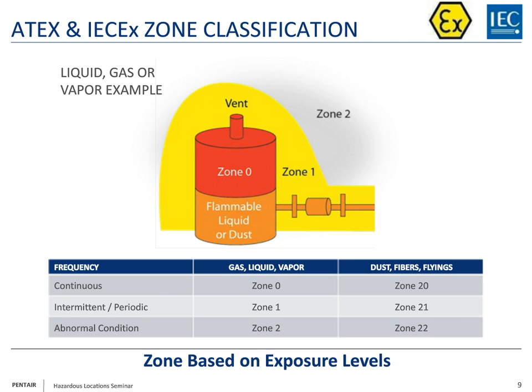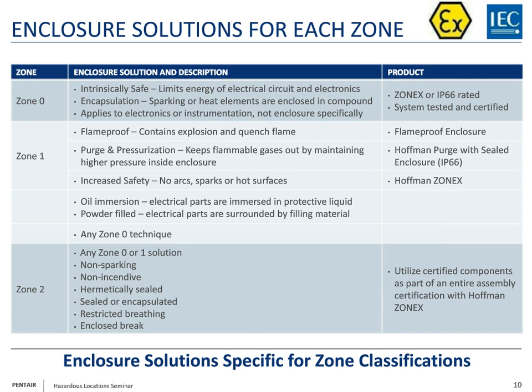So if we focus on zone 0, 1, and 2, what types of solutions are available to you? Well, like I said before, a zone 0, typically you don't see a lot of control panel applications there, but what you do see is low power instrumentation, like pressure and temperature transmitters. Really the idea is you're limiting the amount of energy in the electrical circuit to those transmitters, so you really can't create a dangerous situation. If you were for some reason needing to have a control panel that was Zone 0 certified, which would be really rare, you would need to have that entire system tested and certified by a third party.